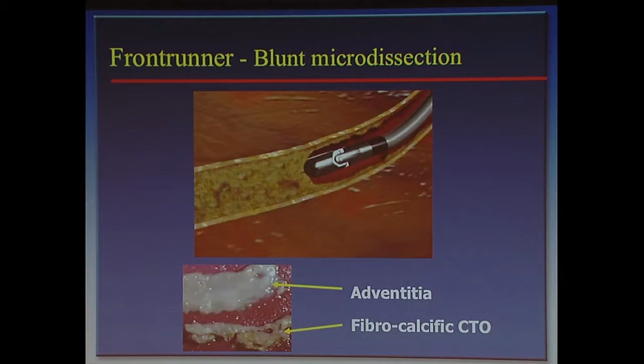The fibrous plaque here, which is the blockage in the actual true vessel, is very hard, so this is able to burrow through that, whereas the vessel wall itself has this adventitia, which is very elastic, and the device would actually deflect off of that. So it's harder to go outside the vessel and create a perforation with a blunt device compared to a sharp needle with the wire that we were using before. It's got some disadvantages as well, but it's a good device in its time. Now we've come along since that.